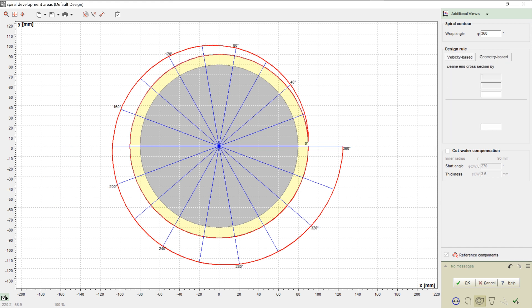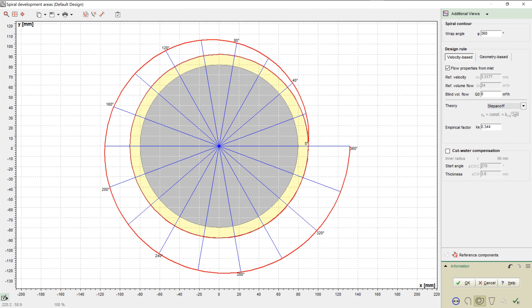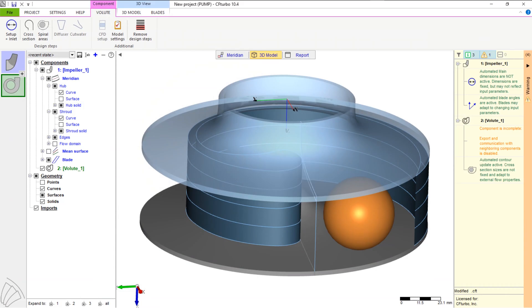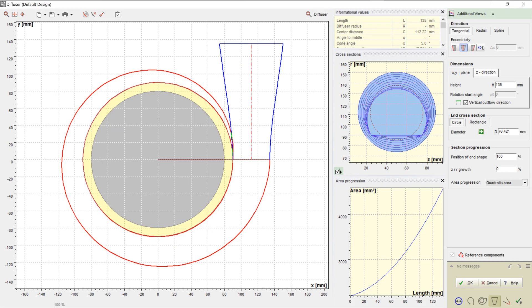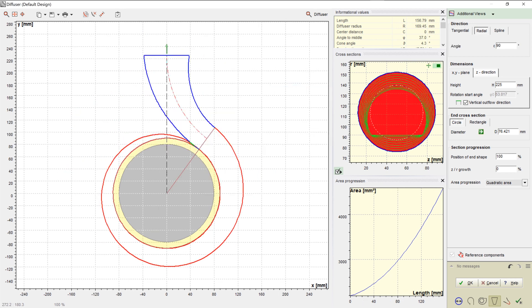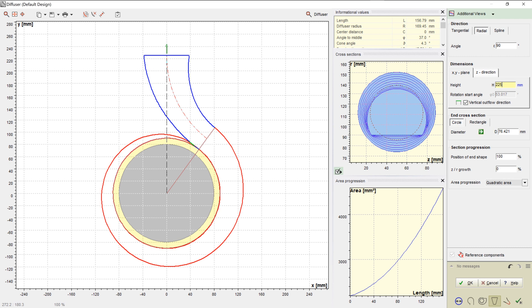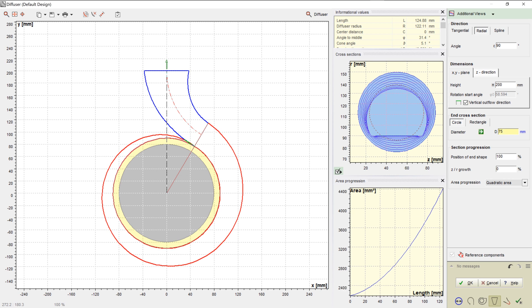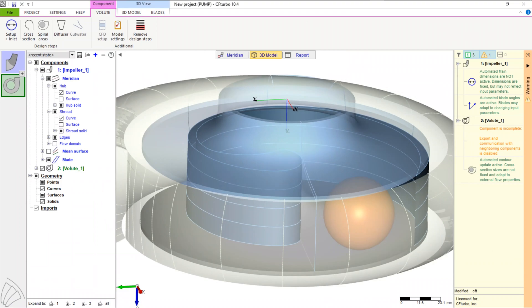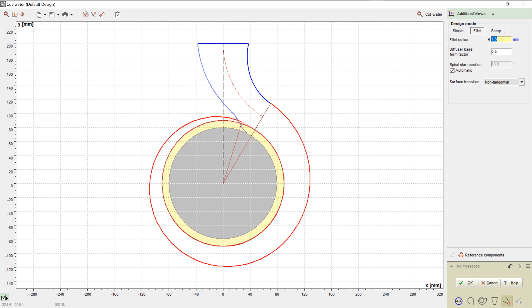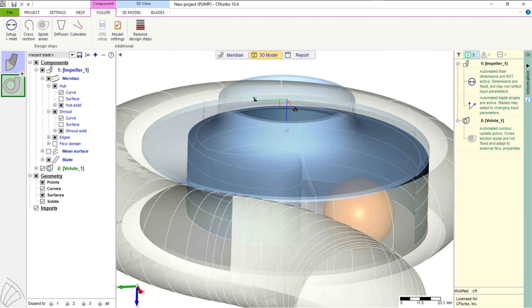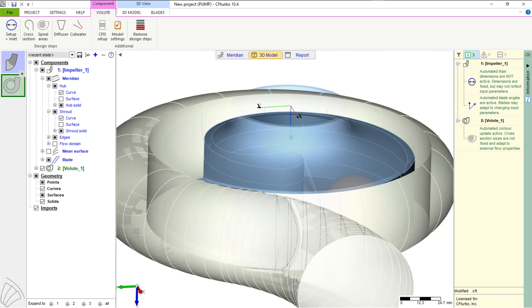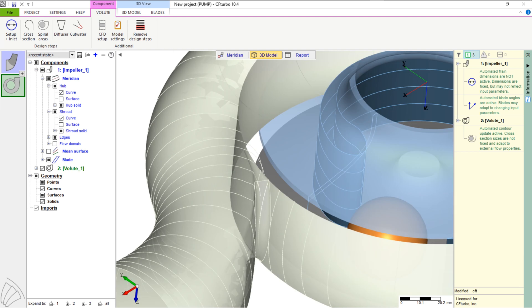Additionally, the user can create the spiral shape by their own geometrical requirements using the so-called geometry based design mode. The influence of the cutwater thickness to the spiral shape can be considered by a correction factor. The discharge diffuser could be radial, tangential, or spline based. Here we choose the radial version for the diffuser. We can adjust the length of the discharge diffuser as well as the discharge diameter and, to some extent, the position of the diffuser in Z direction. Finally, we create a fillet radius which represents the cutwater of the volute. Besides the fillet cutwater option, the user can go for so-called simple or sharp cutwater design.